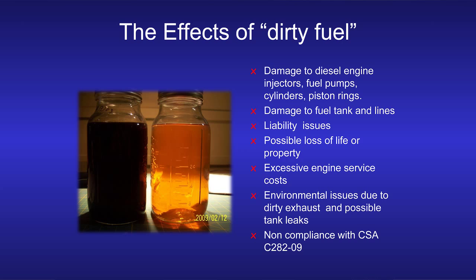Diesel fuel is susceptible to bacterial growth, and if there is water from condensation mixed in with the fuel, it supports the bacterial growth even more and promotes it. The one on the left there is probably the worst case example of what you might see coming out of the bottom of a fuel tank. That can cause problems all through your fuel system, besides the fact that it doesn't comply. So on an annual basis, we take a sample, and if you have dirty fuel, we will give you an estimate to clean the fuel by pumping it out, filtering it and putting it back in the tank over the course of maybe 2 or 3 or 4 hours, depending on how much fuel there is.